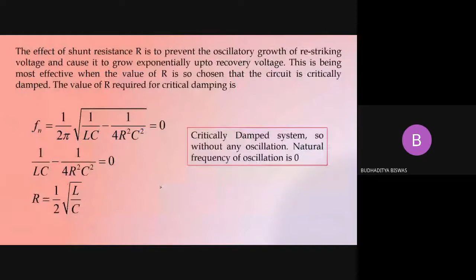To sum up, this is the gist of whatever we learned in this particular chapter, current chopping. A resistor across the breaker contact may be used to perform one or more of the following functions. Number one, to reduce the rate of rise of the restriking voltage and the peak value of the restriking voltage. Because there is no oscillation, it grows slowly and ultimately comes to the recovery voltage. So the natural frequency of oscillation is 0 if we put the exact value of the resistance across the circuit breaker contact. So this is point number one.